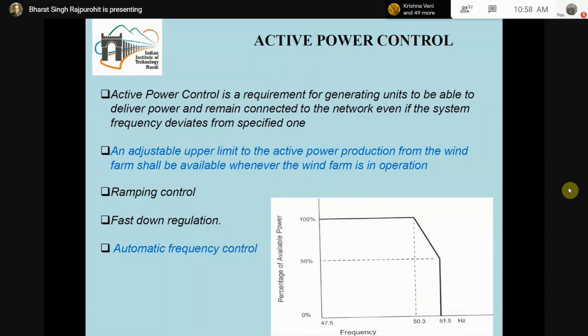And finally, which is the strictest requirement, is known as automatic frequency control. It means that as the frequency is changing in the grid, the wind farm should be able to increase or decrease the active power so that it can participate in maintaining the frequency. Here we see that it is not really possible, because the wind is not in our control. That's why we are not able to increase the output power from a wind farm. So this is a limitation. How to address this limitation? Because you cannot increase the active power from the wind farm, since wind is not in our control.